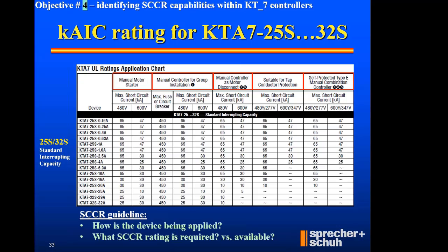And then lastly, self-protected type E. That's the one that we're totally interested in, the far right hand column. I need to point out to you, if you're using 480 volt, no longer is it a delta connection, it's a Y connection at the top of the column heading. I've got the approval for 480Y that, if I'm a self-protected manual combo controller, it's a combination starter. I can still get 65 KAIC with that device by itself with a TE adapter on top of it for the 2-inch creepage space. But agreed, that's what provides me the self-protected type E approval.